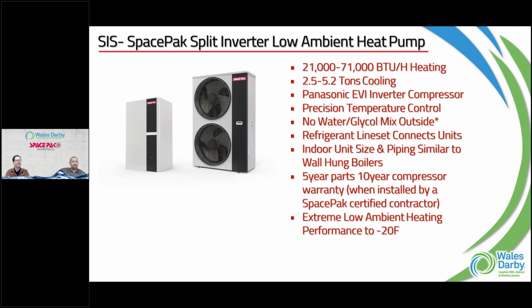So then we get into the split system. Everything I just talked about in the beginning was all monoblock system, right? Where refrigerant's all contained inside the system. This is a little different. This is a two-part system. You've got your outdoor unit, then you've got your indoor unit. That indoor unit kind of looks like a wall-hung boiler. That's going to house our refrigerant to water heat exchanger. So in this case, we do need a refrigerant license because we are going to be running a line set from the indoor to the outdoor, right?